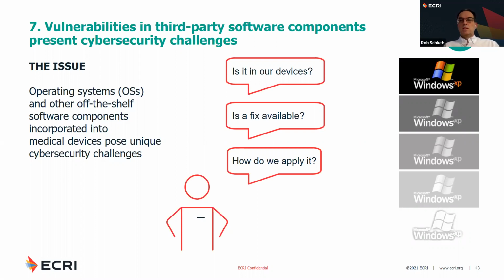The trick is it's not always easy to tell when that kind of software is being used in a medical device. Like in my case, I'm looking at my laptop here. I know it runs the Windows operating system, but the medical device doesn't have a screen or may not use an operating system in that same manner, so I may not be aware of what's inside that black box. So when you learn about a software vulnerability, the first challenge is figuring out which of your medical devices could be affected by that vulnerability. And that's before you even get to the challenges related to getting a fix and then applying it in a healthcare setting, which we'll talk about in a second.